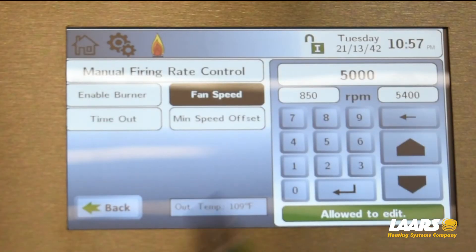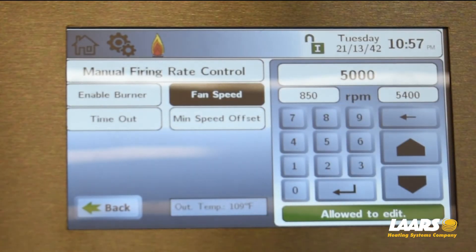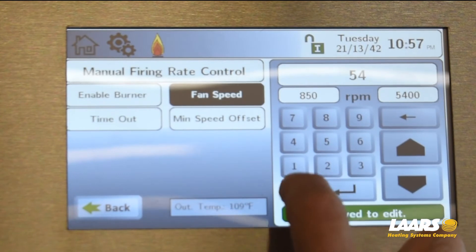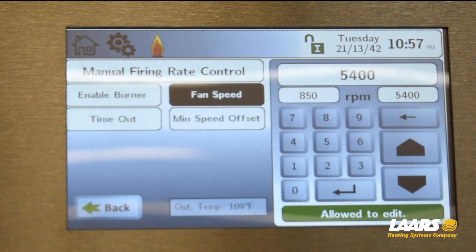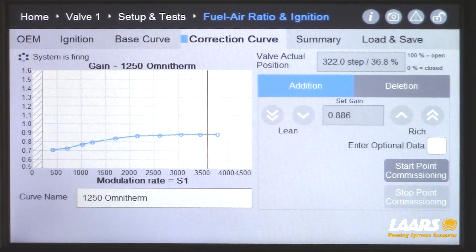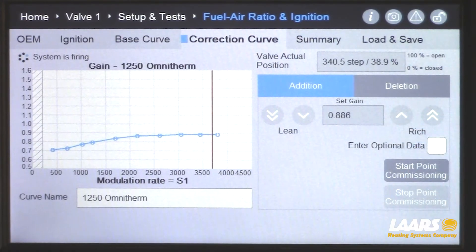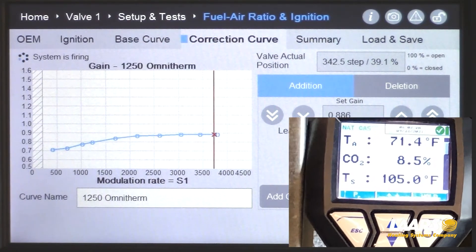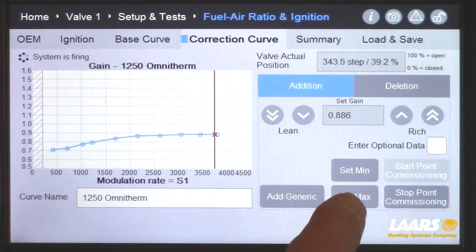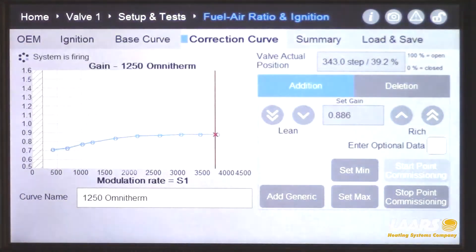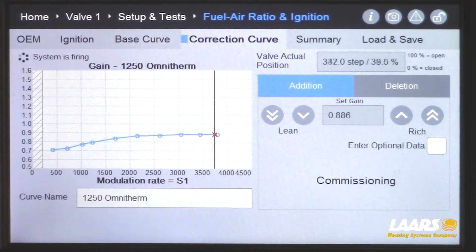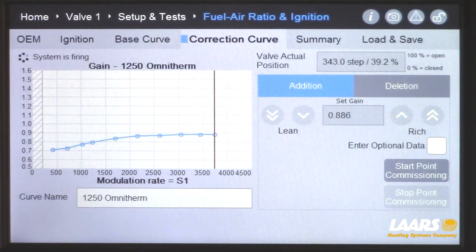The last point will be 5400 — that's close enough to 5000, so we can't go to 5500. Back that out and type 5400, press enter. Go back to your gas valve display and wait for the indicator line to come up. Keep in mind that this is set max — not set generic. Click start point commissioning, check combustion, and right here is set max. Press set max and click yes. If there's an additional point, it will pull over because it was set max. Your combustion is now complete.